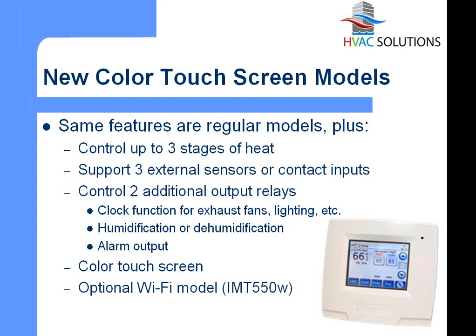On the output side, there are additional outputs as well. In addition to a third stage of heat output, you could also have 2 output relays unrelated to the furnace or rooftop you're controlling. The old models used to have 1 extra output relay for a humidifier or dehumidifier, but these have 2 outputs. You can use them for a humidifier, a dehumidifier, or both, or as a time clock function to enable exhaust fans in a commercial building, turn on exterior lighting in a parking lot or porch, or turn on a sprinkler system, whatever you want based on time.